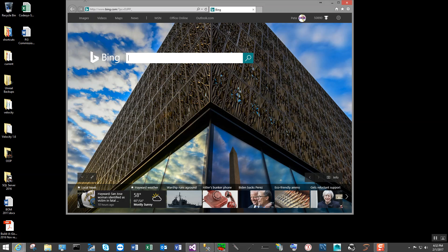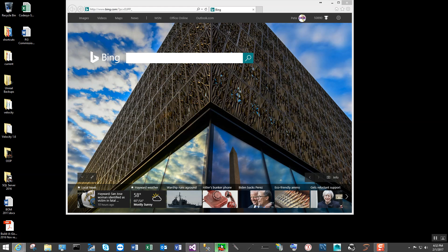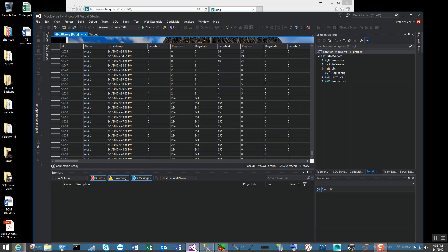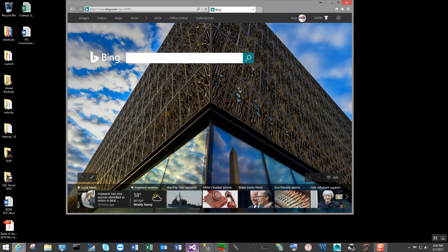Reports from Power BI are like looking at the long-term or bigger picture of your data. The smartphone apps we typically work with on buildagizmo.com are for literally controlling the equipment in real-time. So there are two different ways of dealing with your data: one is a real-time solution, and the other is for building reports. The reports need a historical gathering place — from this Modbus device into the SQL Server — to gather the data so that you can report on it and the charts work correctly.